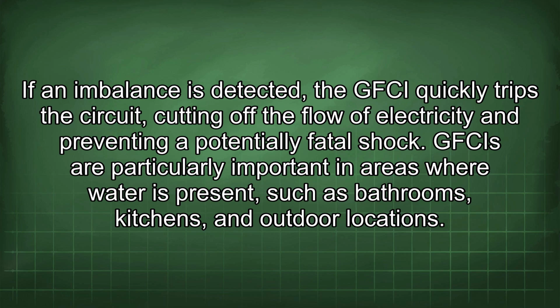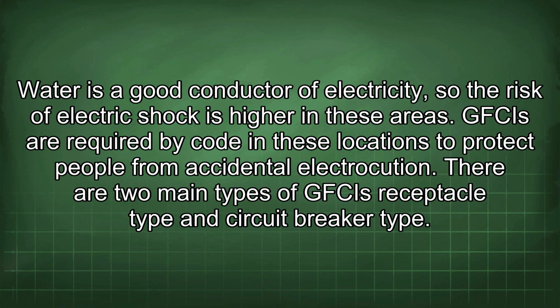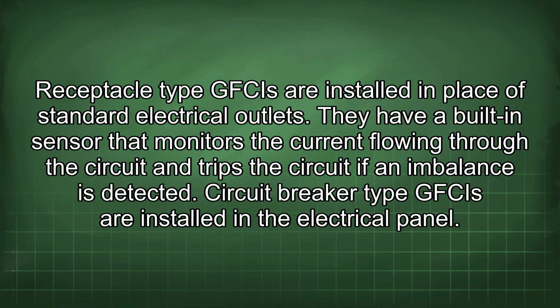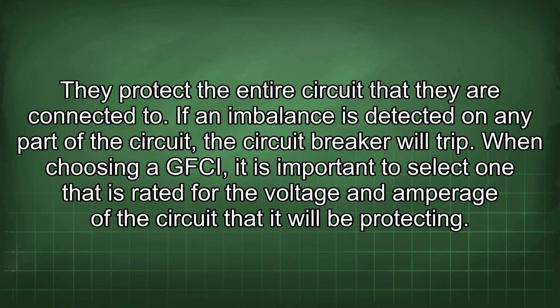a potentially fatal shock. GFCIs are particularly important in areas where water is present, such as bathrooms, kitchens, and outdoor locations. Water is a good conductor of electricity, so the risk of electric shock is higher in these areas. GFCIs are required by code in these locations to protect people from accidental electrocution. There are two main types of GFCIs: receptacle type and circuit breaker type. Receptacle type GFCIs are installed in place of standard electrical outlets. They have a built-in sensor that monitors the current flowing through the circuit and trips the circuit if an imbalance is detected. Circuit breaker type GFCIs are installed in the electrical panel. They protect the entire circuit that they are connected to. If an imbalance is detected on any part of the circuit, the breaker will trip.